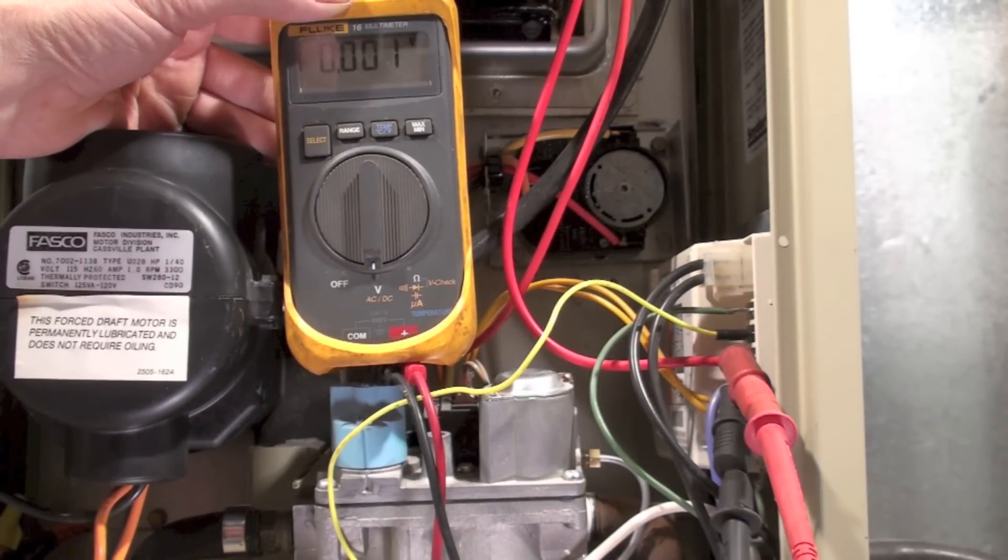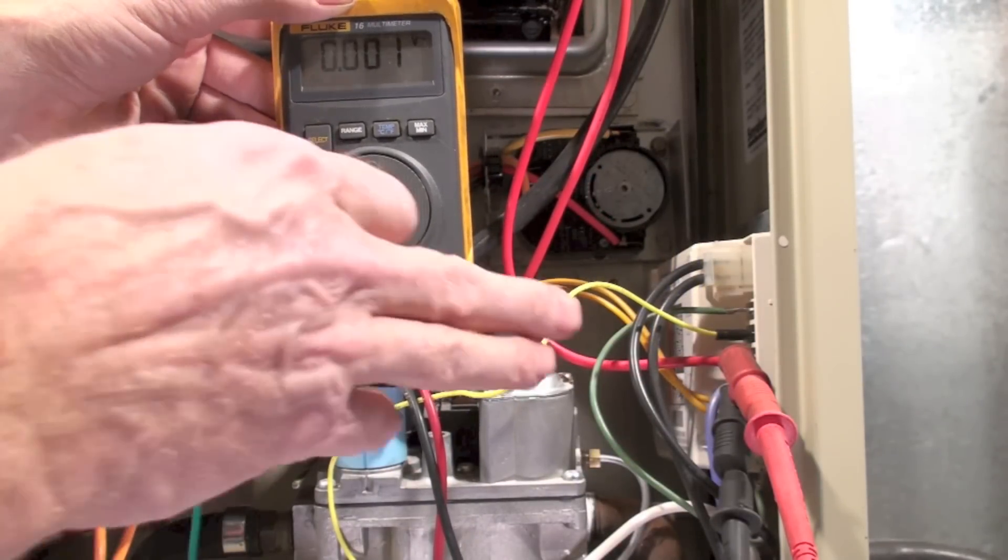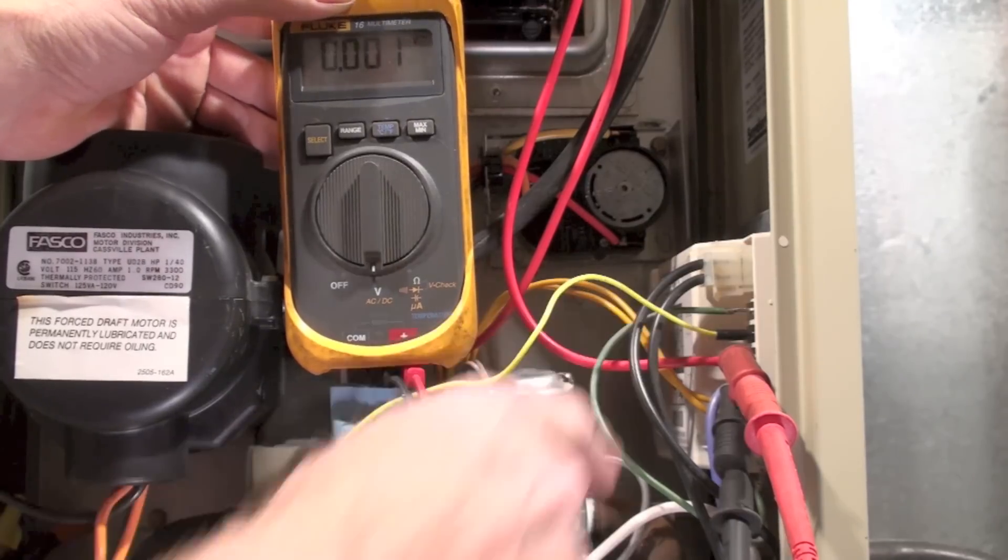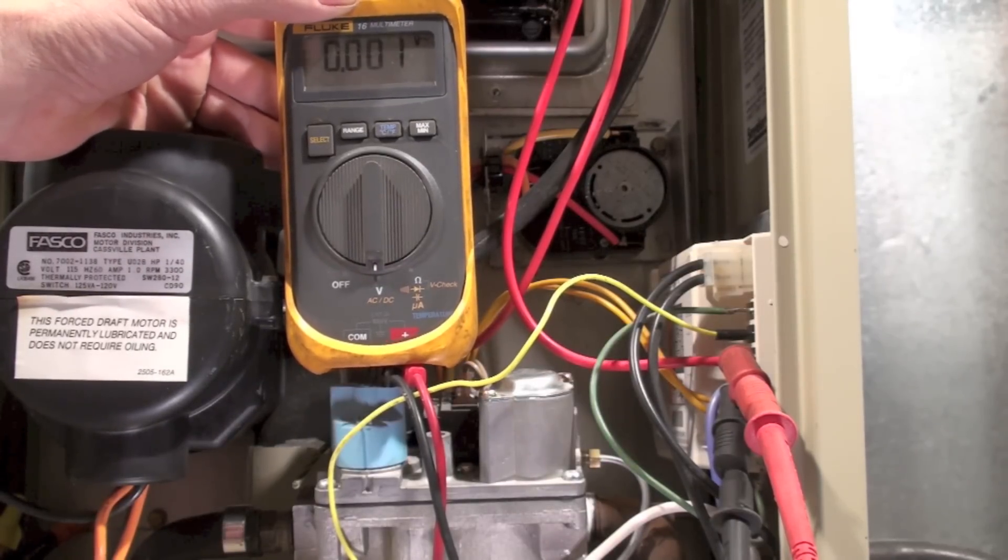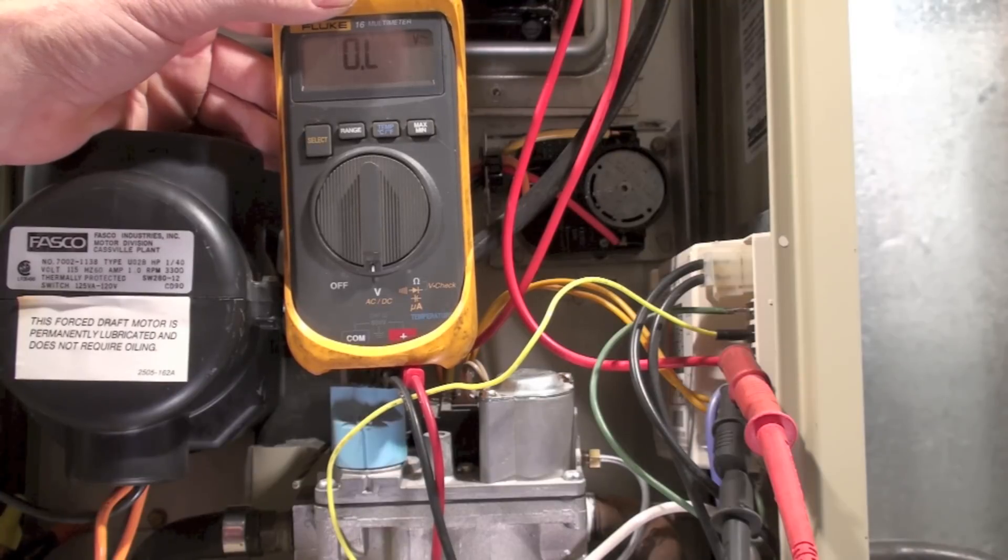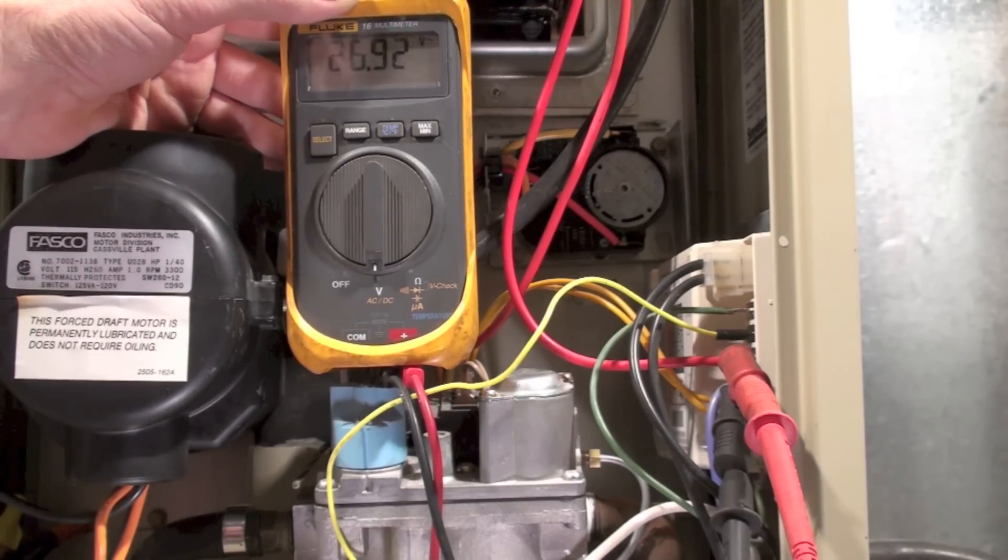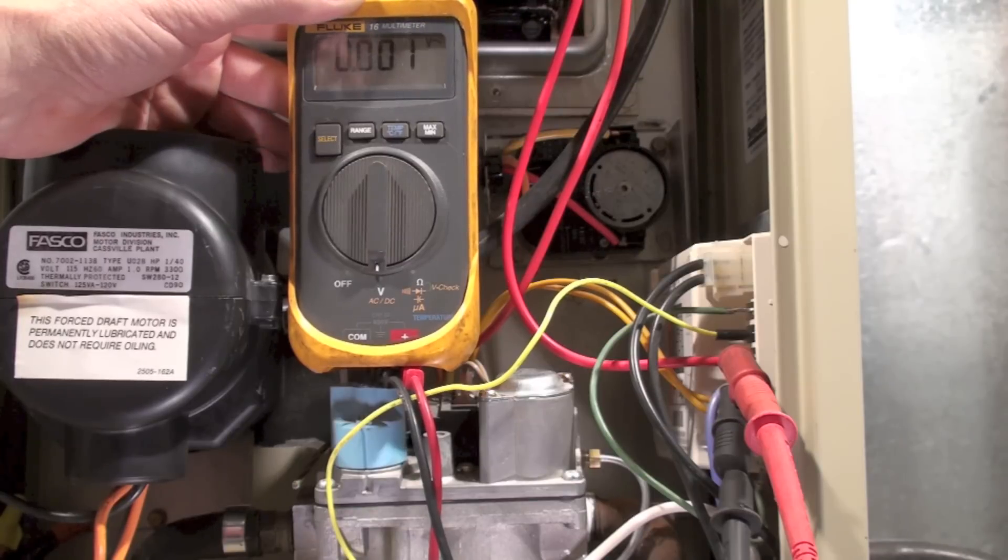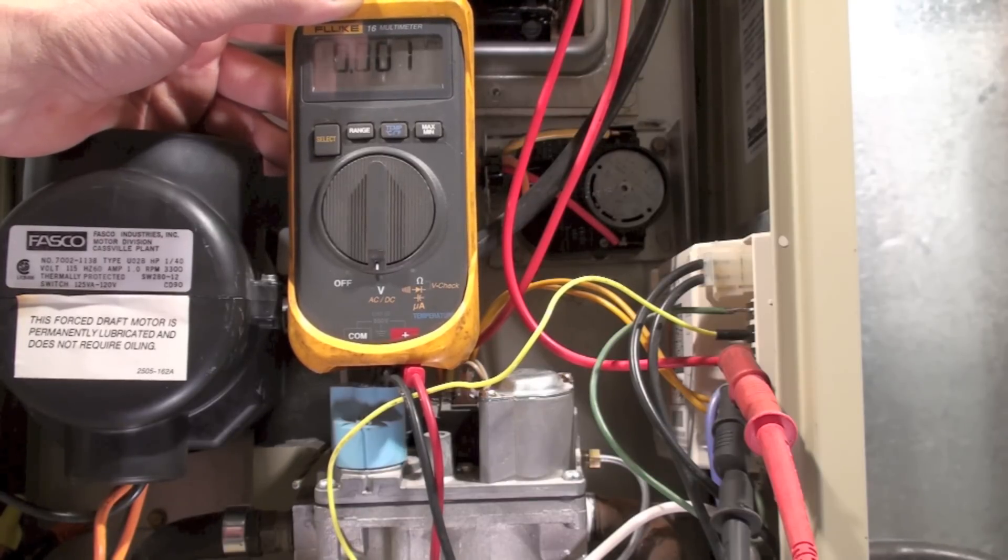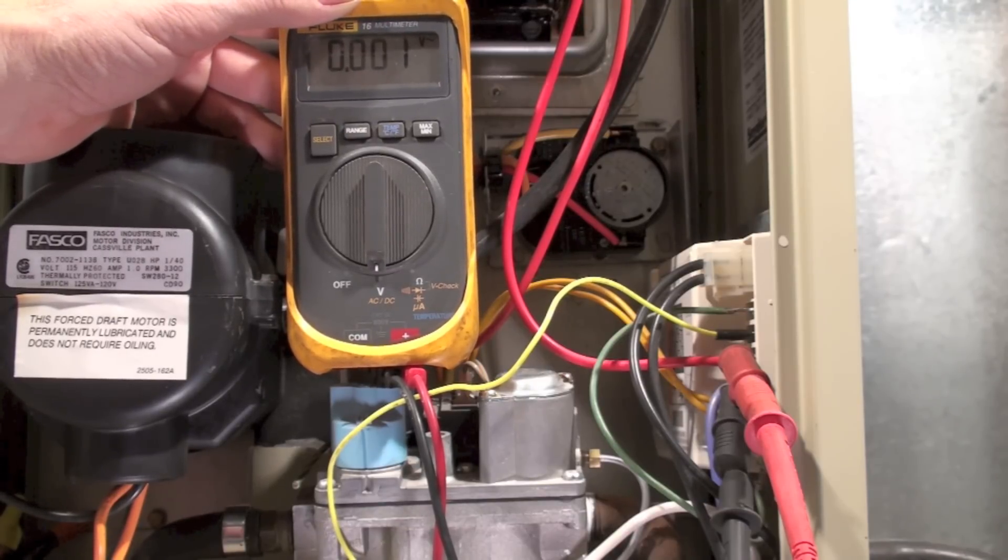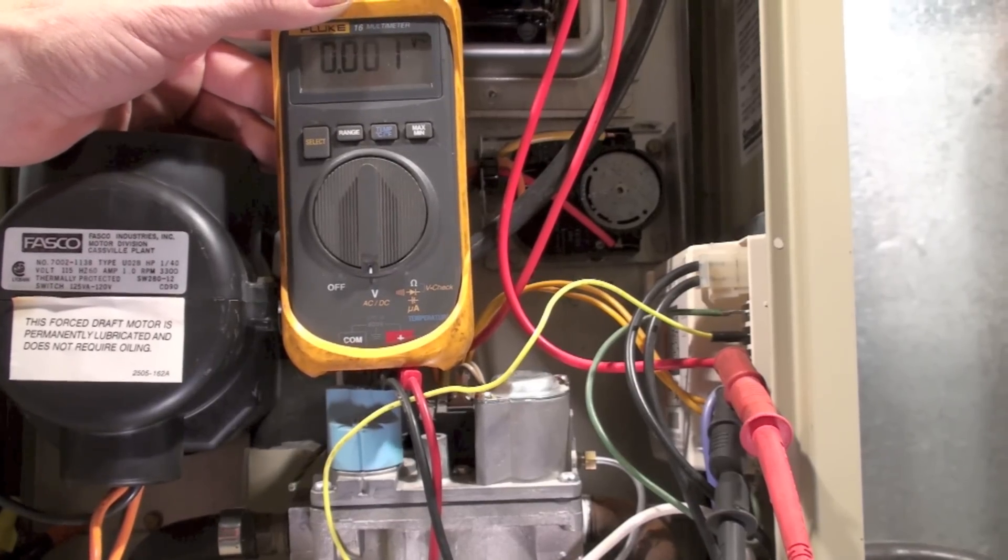Okay, here I've got the probes mounted between TH and TR on the controller, right in there, and I'm going to start this up. Okay, I went to where there's power and then the power went away. Okay, that's pretty much a dead giveaway that you've got a pressure switch problem. Now let's take a look at that pressure switch.